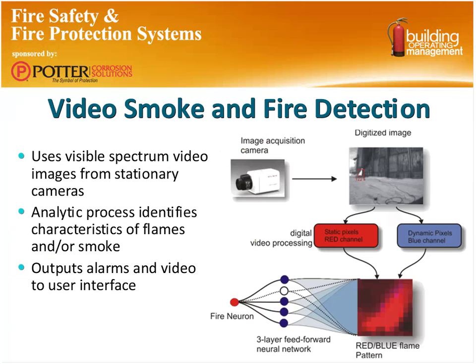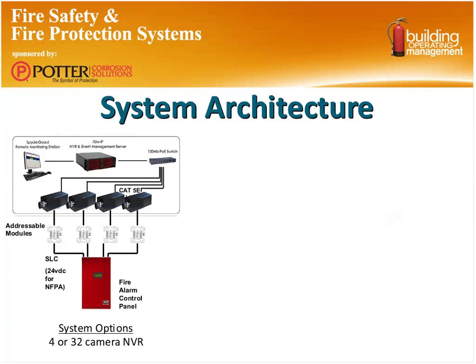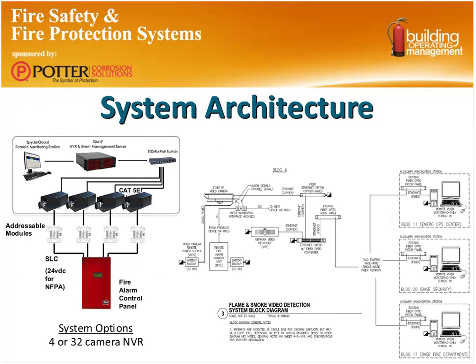So this is a typical layout of what the system is doing. It's a camera. It takes a digitized image. It processes it through different channels, looking at red and blue. If we take that, we can assimilate that into a flame. We can run that through the logic processor and ultimately take an output in some kind of signal format. Typical system architecture looks very normal to a normal fire alarm system with one other component. Up here in this area, we actually have the traditional video recording architecture. Down in this section, we have the traditional fire alarm architecture. By combining the two of those, we can gain the best of both worlds.